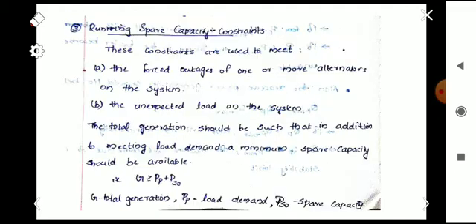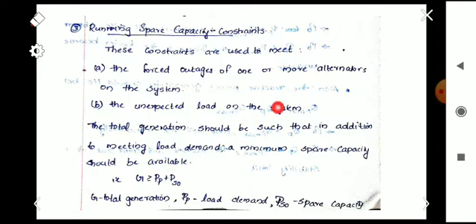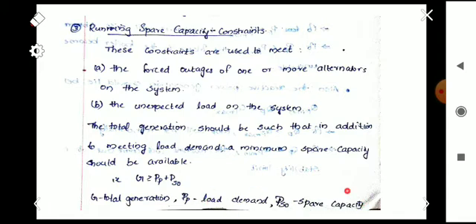The third inequality constraint is the running spare capacity constraint. These constraints are used to meet forced outages of one or more generators and unexpected load on the system. The total generation should be such that, in addition to meeting load demand, a minimum spare capacity is available. That is, total generation ≥ Pp + Ps0, where Pp is the load demand and Ps0 is the spare capacity needed for sudden unexpected load demands.